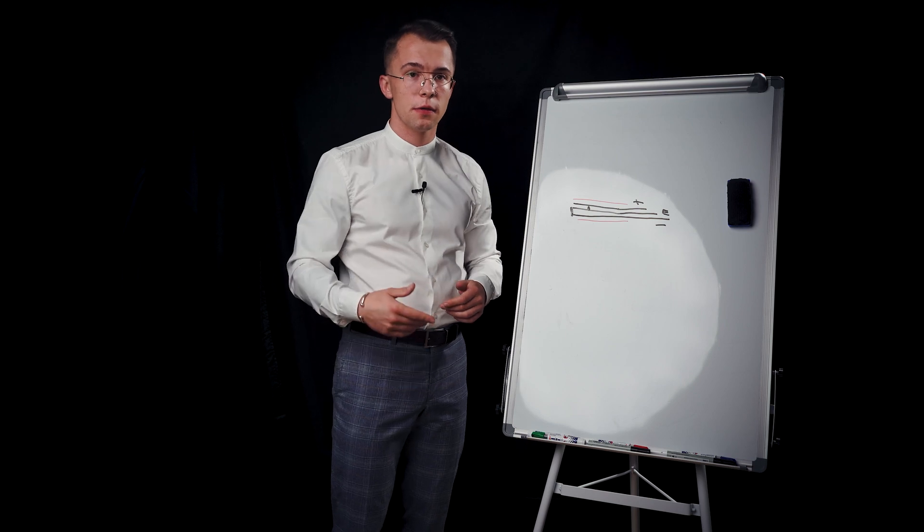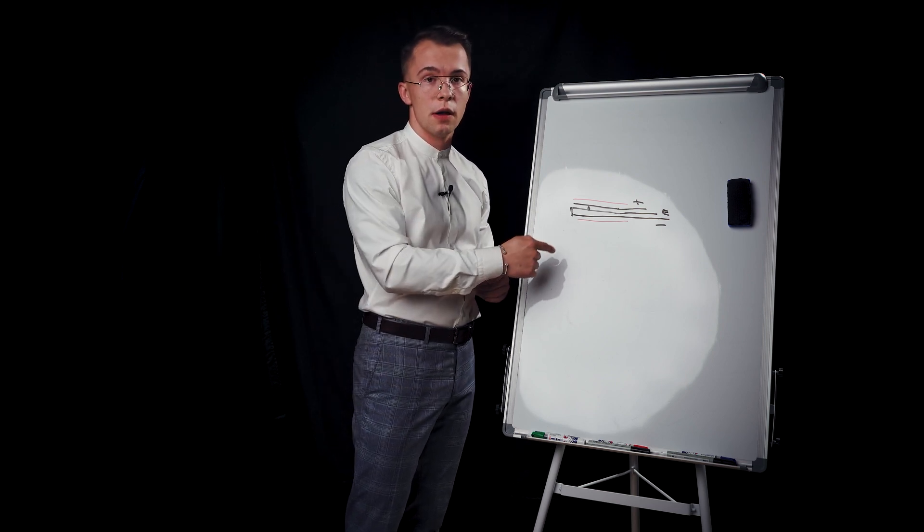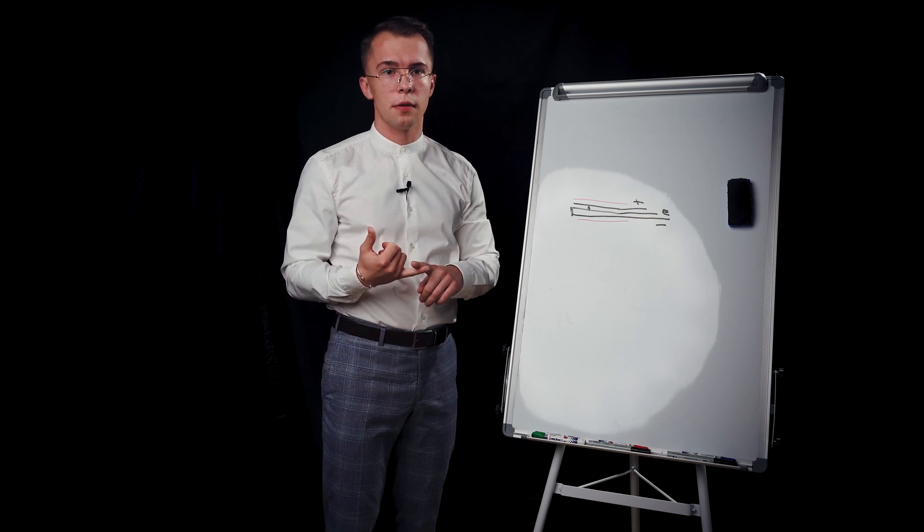Another thing you're checking is the loops. To check if your loop is causing an earth fault, you'll have to disconnect one loop, for example the first loop, then check if the earth fault remains. That way you're checking all your loops one by one.